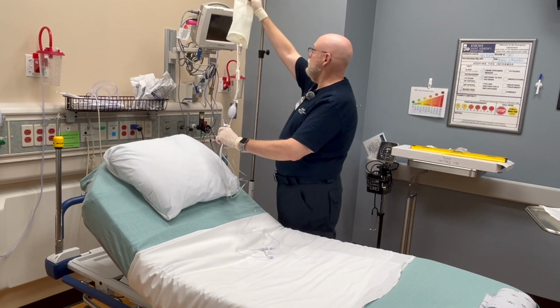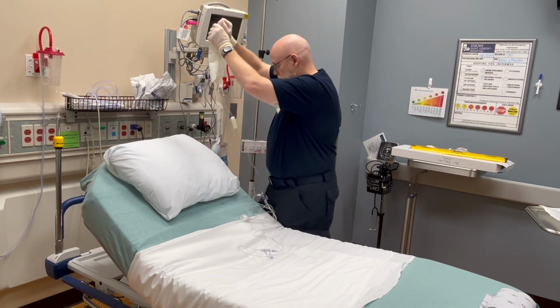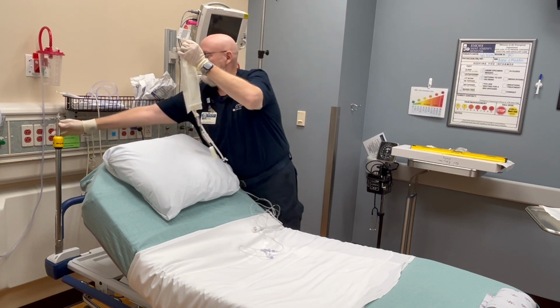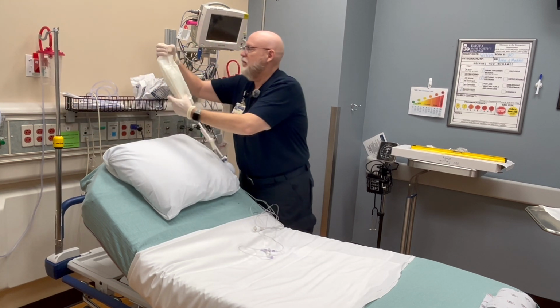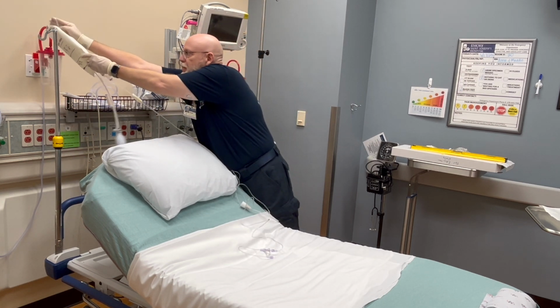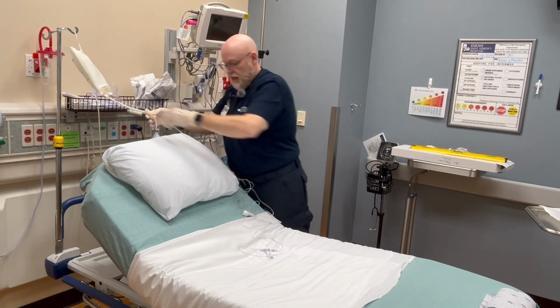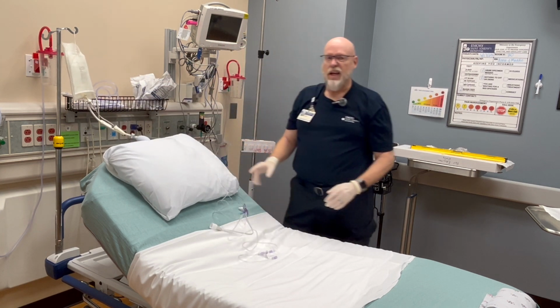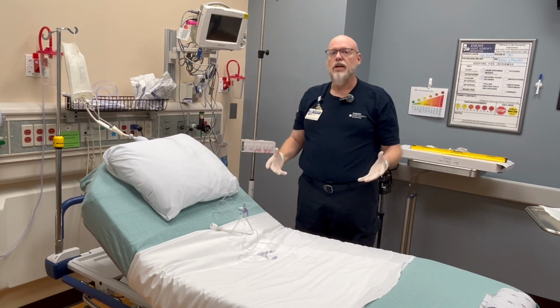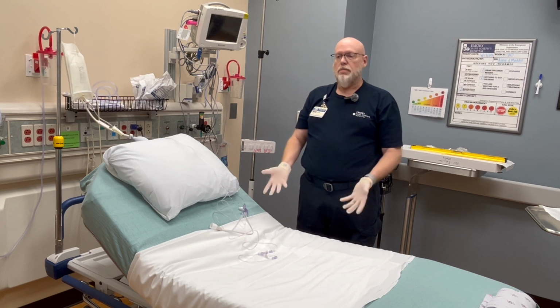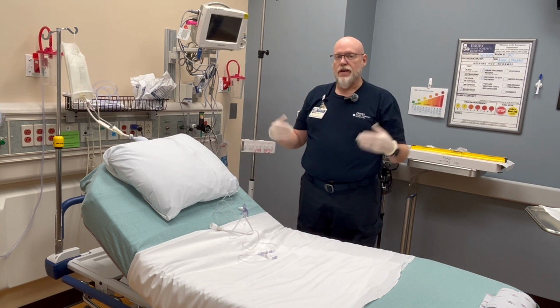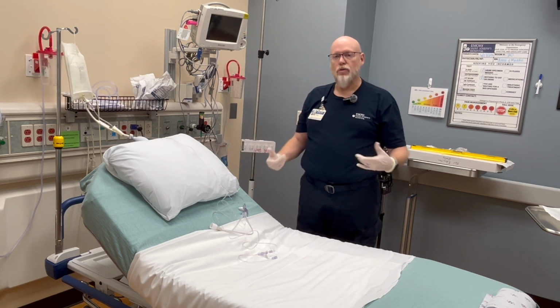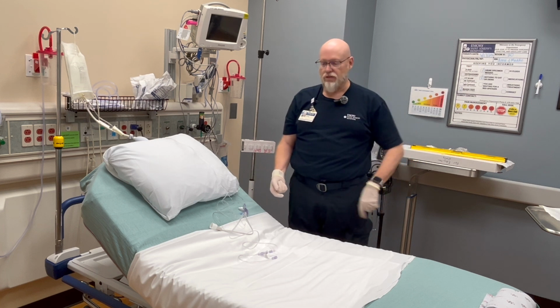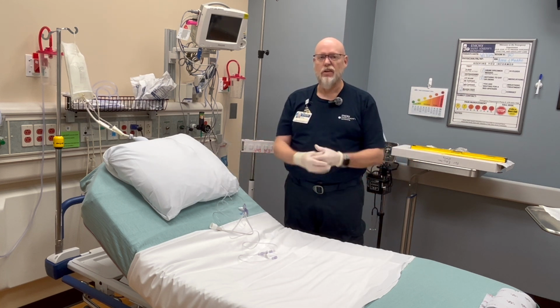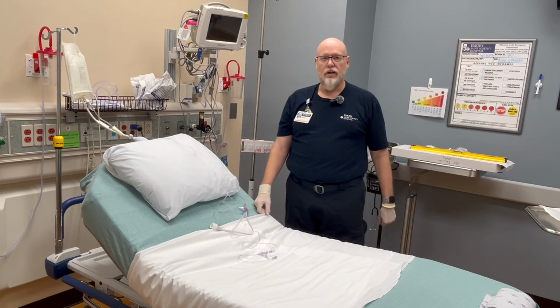Then you're going to remove the transducer from the holder, take your IV bag, and put it on the stretcher IV pole, and then transport the patient. Anytime you move the patient who has an A-line, like if you roll them or raise them up or down, you're going to have to re-zero it and level it. So they're going to have to do that once you get upstairs to ICU. Once they get the patient settled in, they're going to level it and re-zero it.